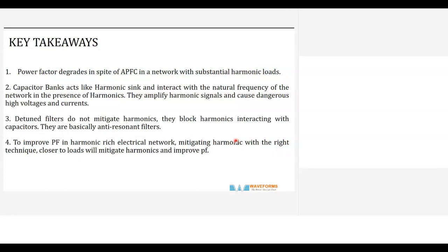So detuned filters do not mitigate harmonics. They block harmonics, interacting with capacitors. The right term would be anti-resonance. To improve power factor in a harmonic-rich electrical bus, mitigating harmonics closer to the loads will mitigate harmonics and improve power factor. So when you mitigate harmonics, you improve power factor also. That's a very key, important point.